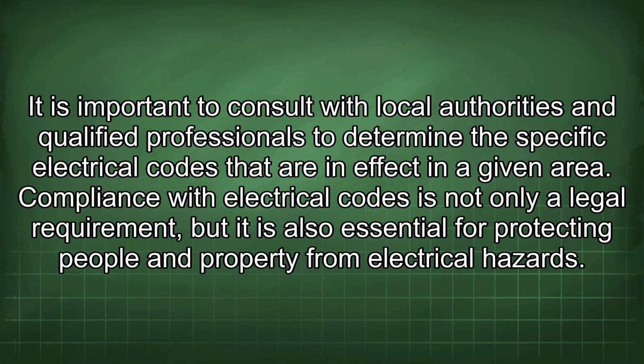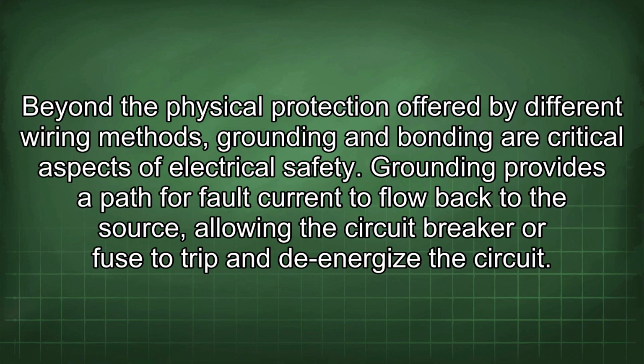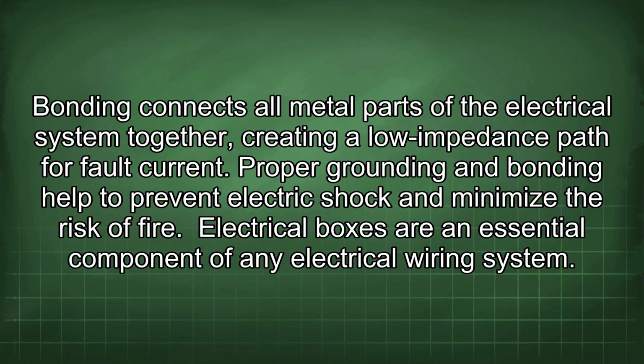Compliance with electrical codes is not only a legal requirement, but it is also essential for protecting people and property from electrical hazards. Beyond the physical protection offered by different wiring methods, grounding and bonding are critical aspects of electrical safety. Grounding provides a path for fault current to flow back to the source, allowing the circuit breaker or fuse to trip and de-energize the circuit. Bonding connects all metal parts of the electrical system together, creating a low impedance path for fault current. Proper grounding and bonding help to prevent electric shock and minimize the risk of fire.